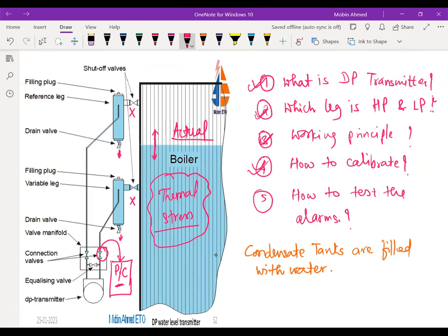So that alarm will come, but you will not come to know exactly at what point it is coming, because actually you are not doing it, and nobody is going to allow us, because a lot of water is going to be drained from the boiler drum. So generally nobody allows that. And second, after the draining, when you fill up the water, it is cold water. So the engineers are not going to allow you to fill up so much water in the boiler.